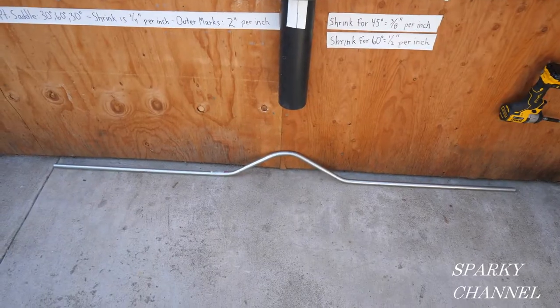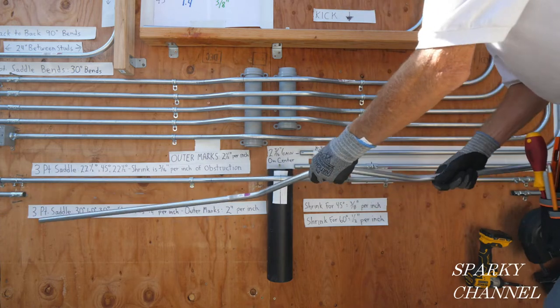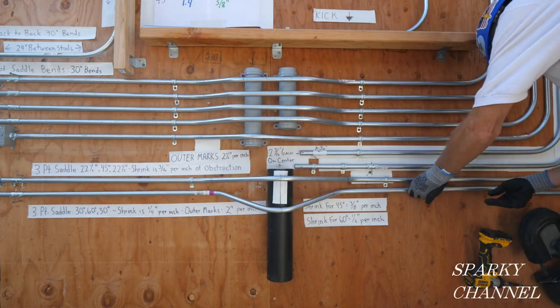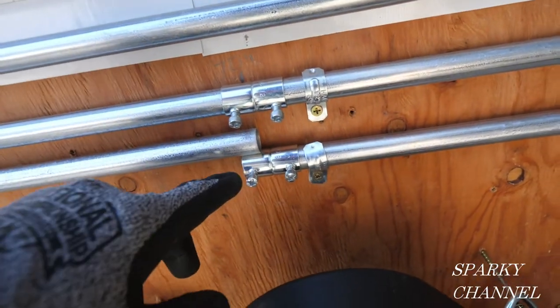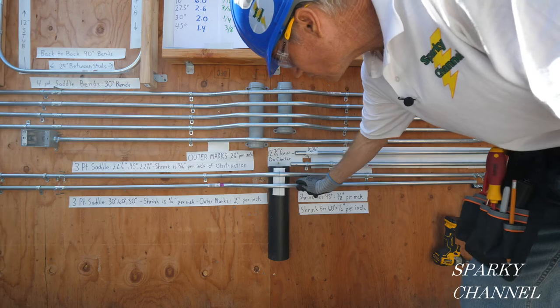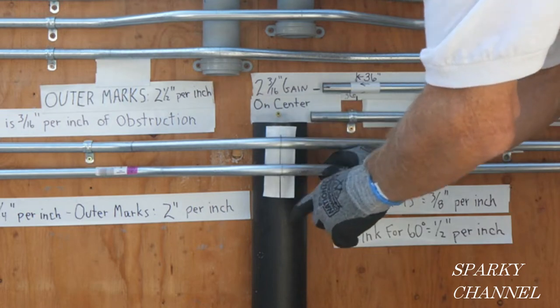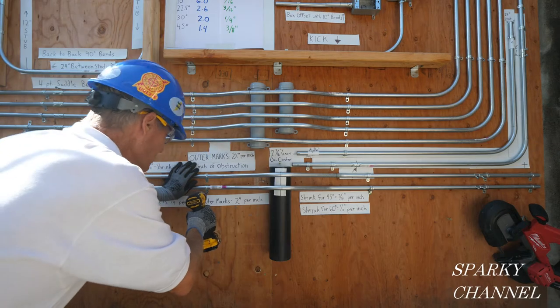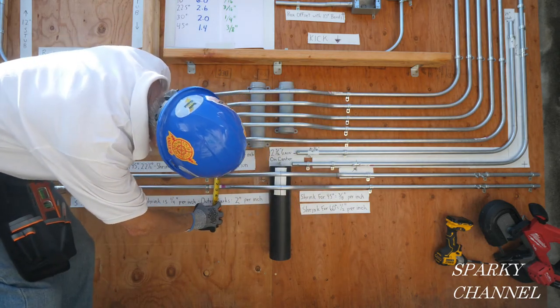There you are — check it on the ground. Here's the conduit; let's see how it fits. We'll put it in the fitting down here — that's looking good. This one looks like it's fitting just right. The conduit came out just right; it'll go into this fitting. Our 72-inch length was just right. Our line is right in line with the center mark on the obstacle.